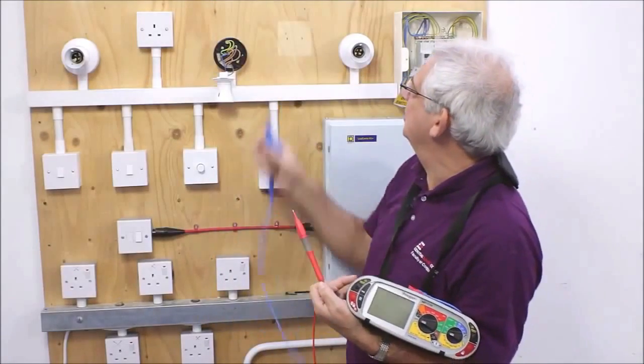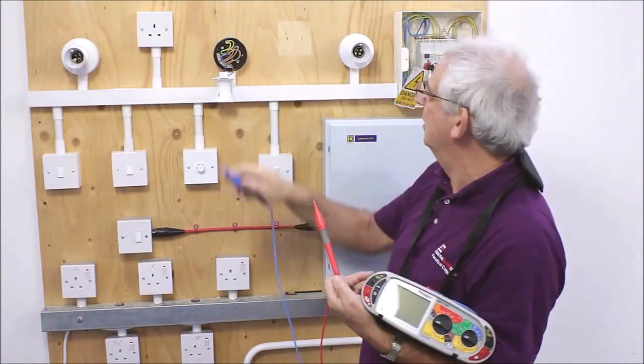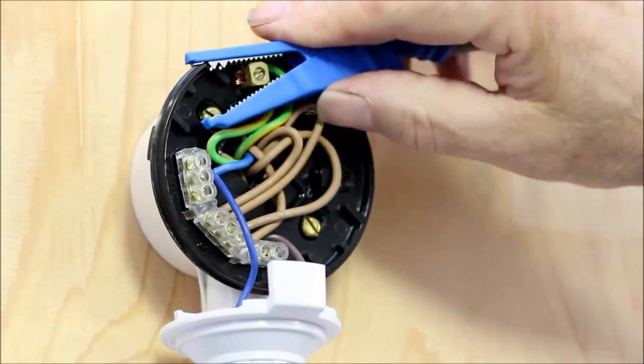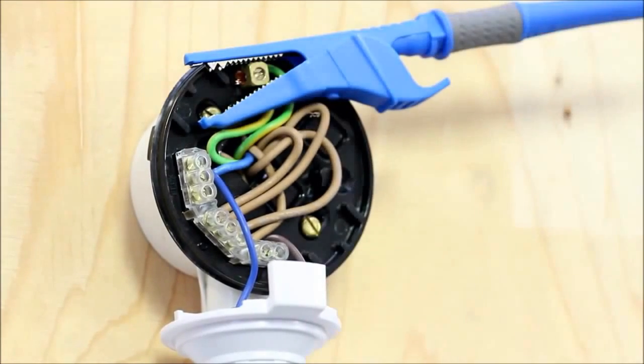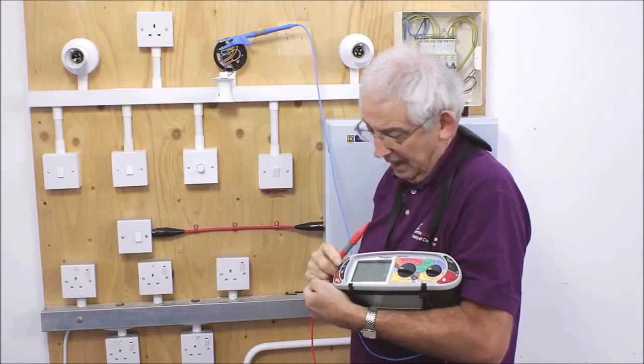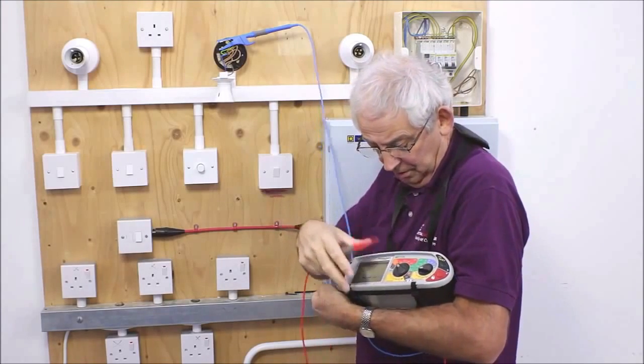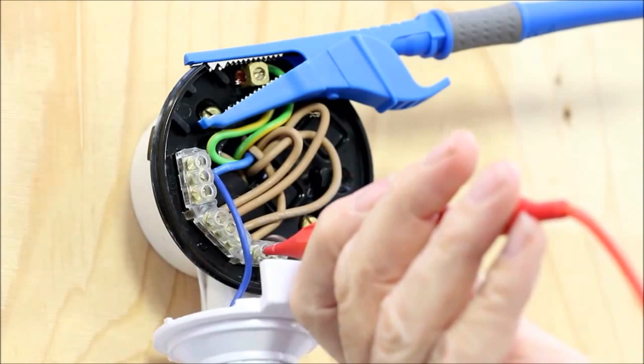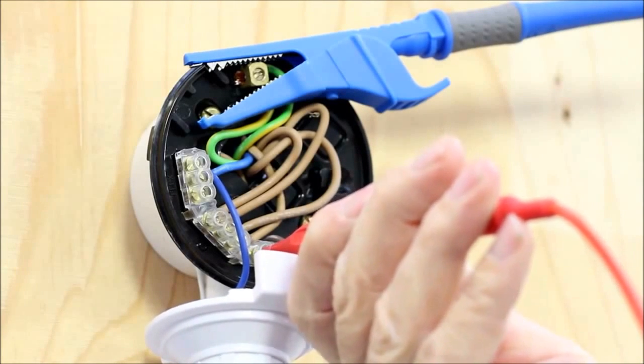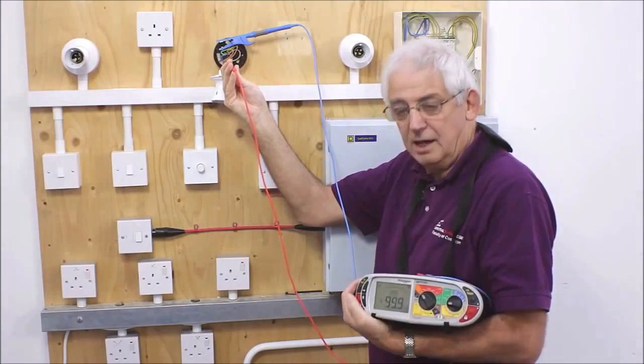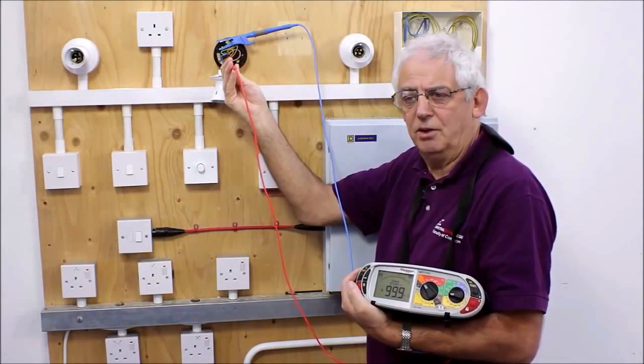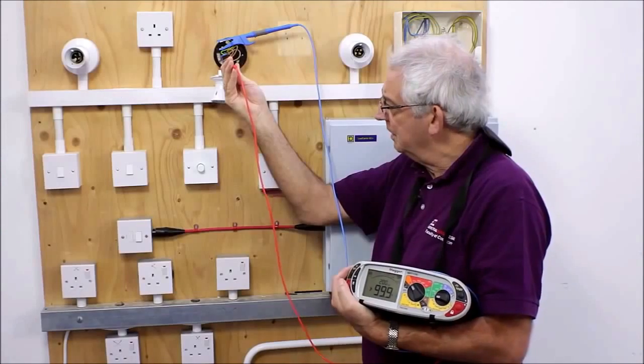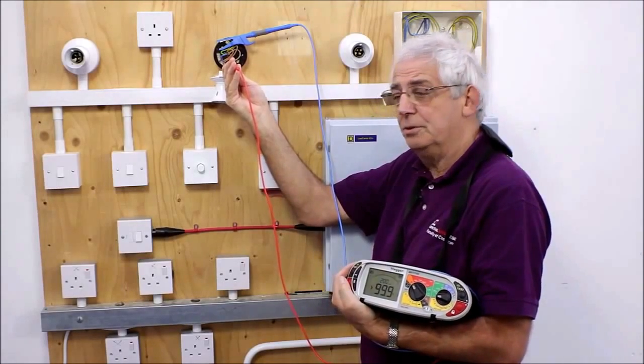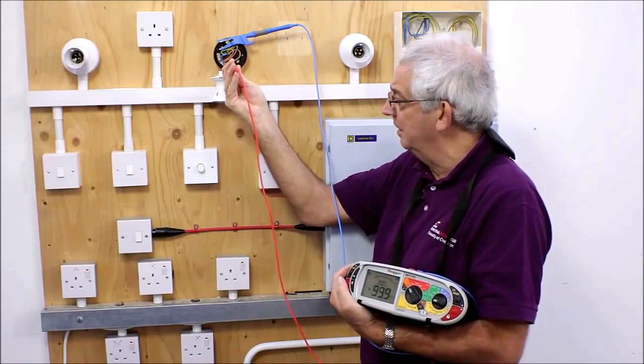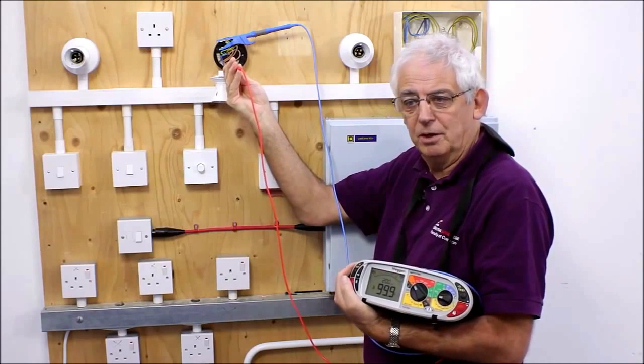So now we've exposed all of the conductors that we need to be working on. I just need to connect my leads. So first of all, one lead goes onto the earthing point of the circuit, and turn the instrument on. We've already zeroed the leads. I now need to place the probe onto the switch return of the lighting circuit. And we can see that I've got an open circuit here. Okay, that's higher than the value can read. What that's really telling me is one of two things. Either I've got the wrong conductors here, or the switch is turned off, which is giving me a high reading.